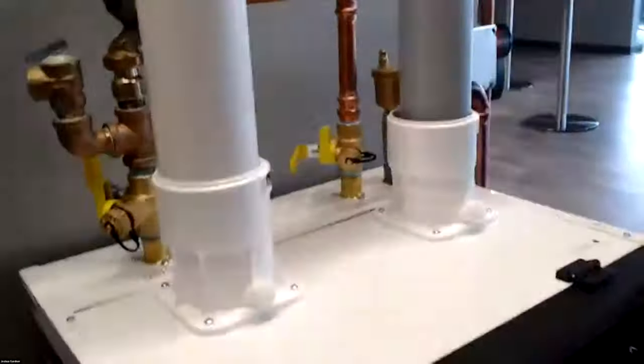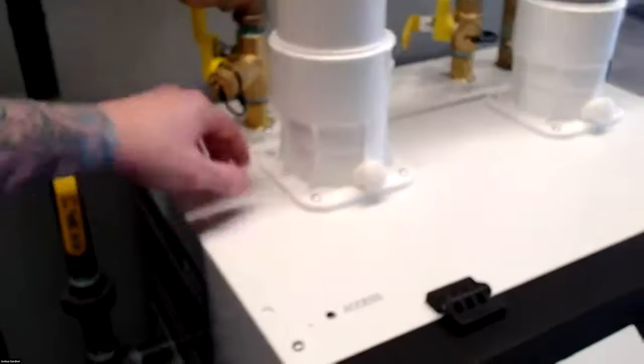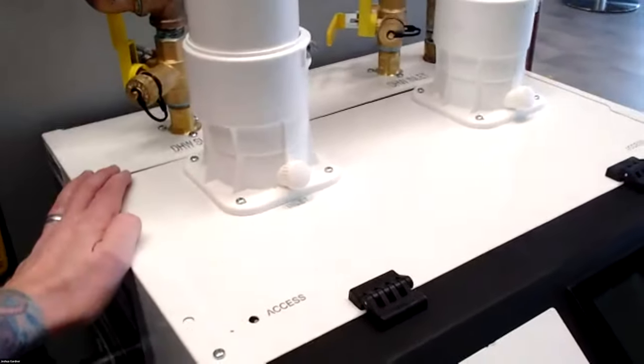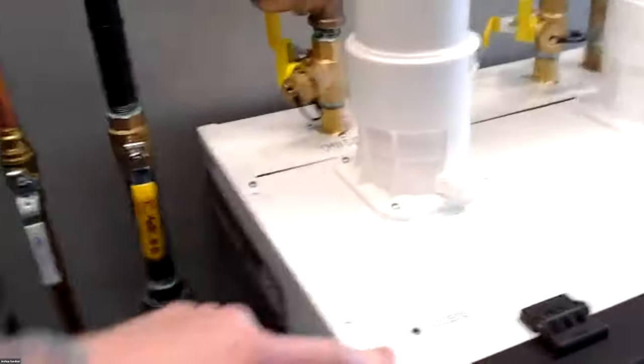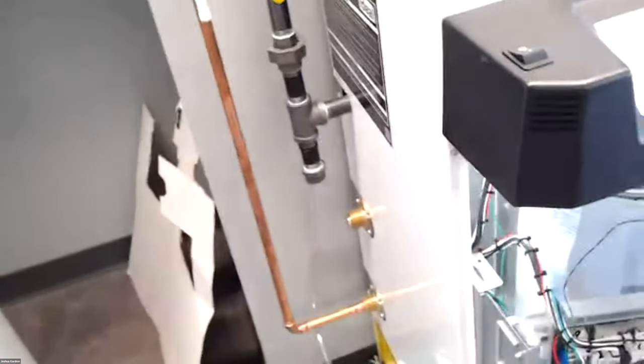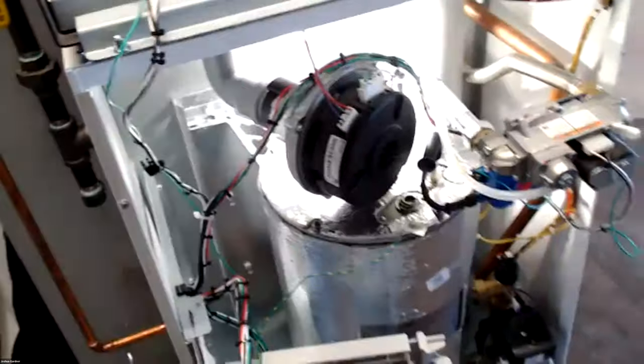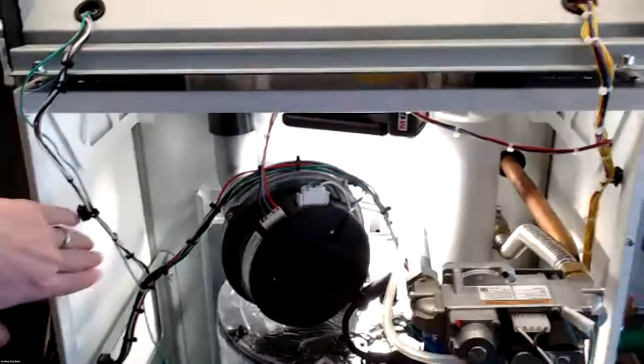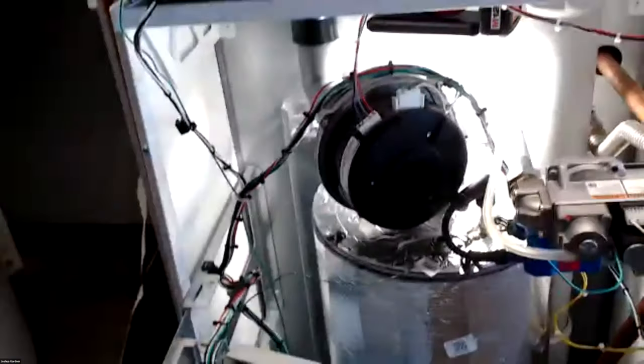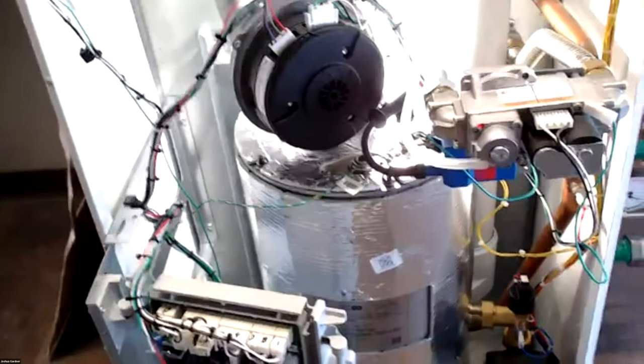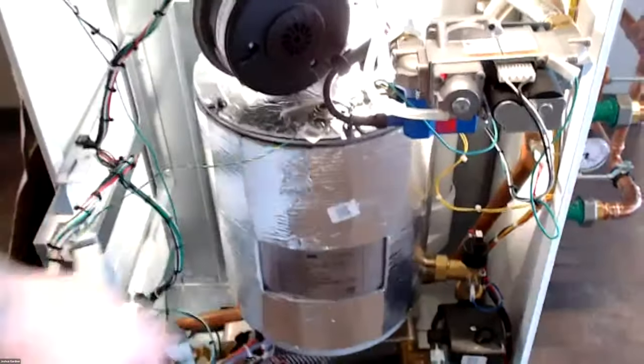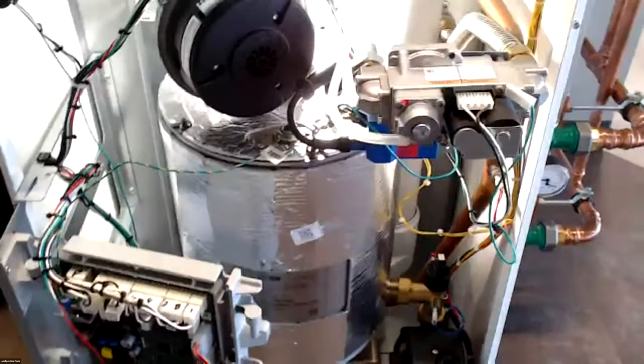Those are the connections. That all being said is even on our wall boilers, I didn't hit on this, but our side panels, our top panels, back panel are all removable. So if you need to gain access to any of this stuff, pop a screw here, pop a screw there, couple on the bottom, this whole side panel comes off. So if you needed to get access to the heat exchanger, you wanted more room, there is a skeleton here that kind of holds it all together. And these side panels and top panels can remove for service. I don't know why you'd really need to, because everything's pretty easy to come out the front, but we give you the option if you want to take off those side panels, you can.